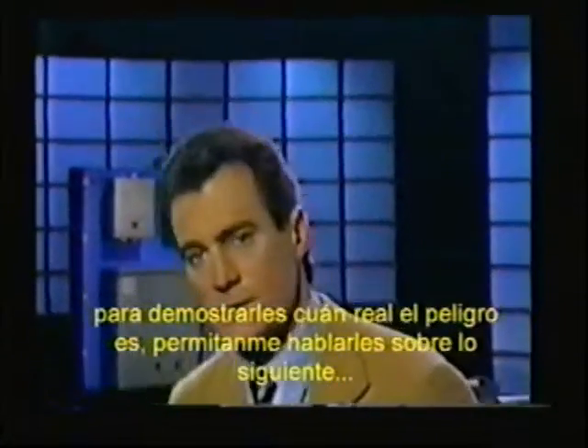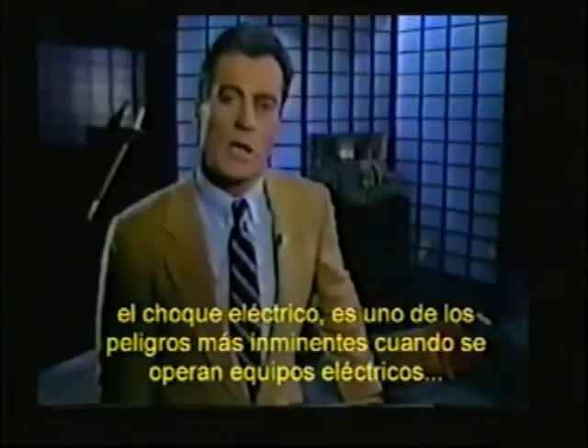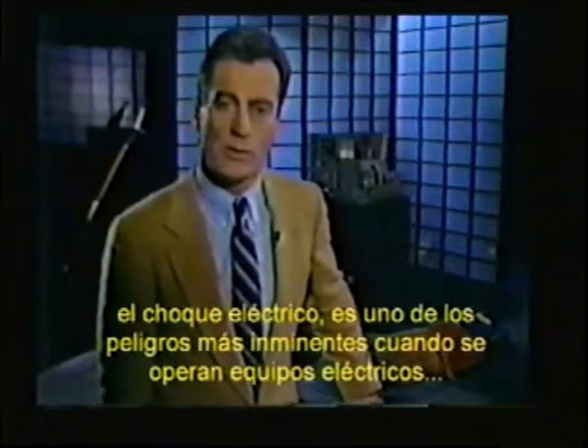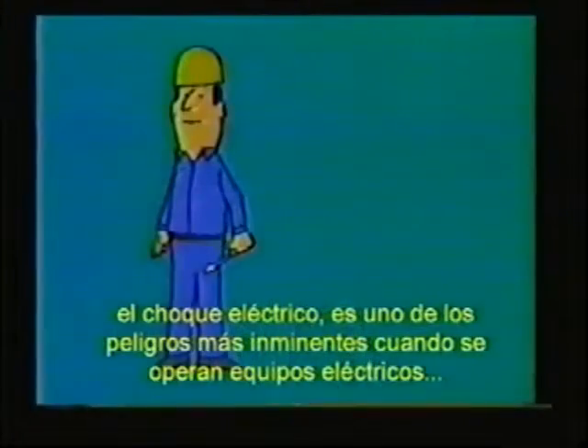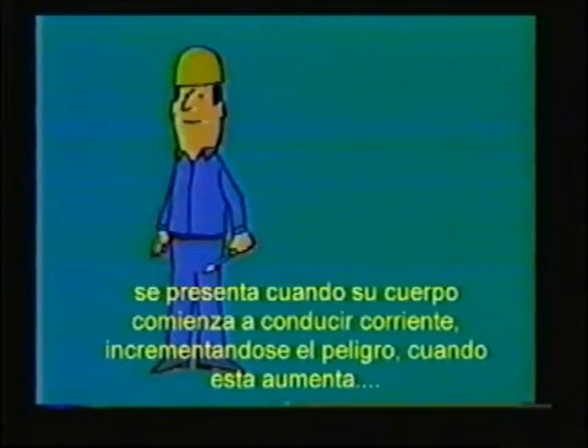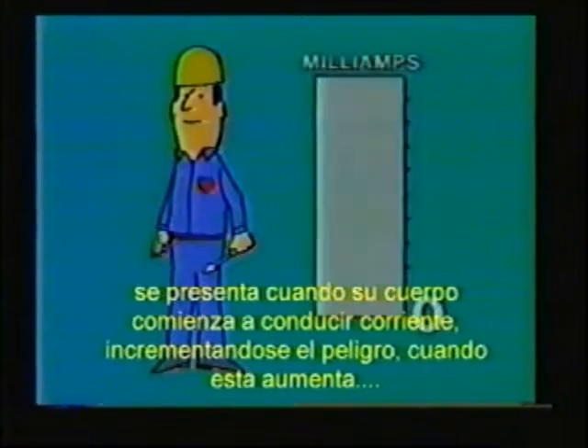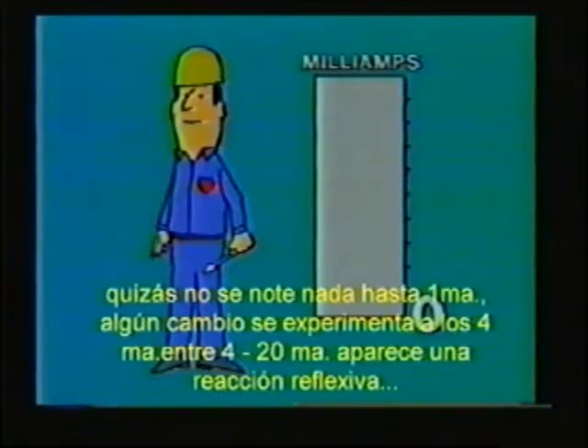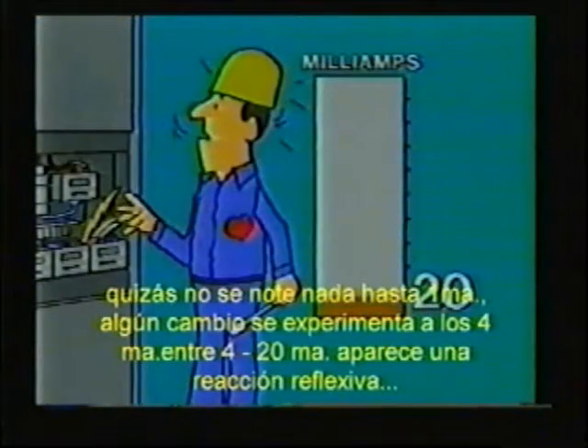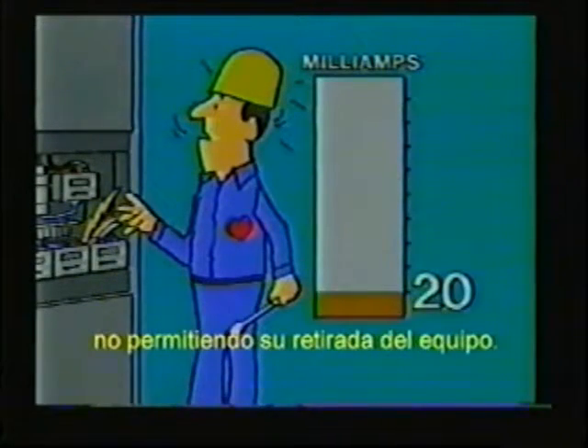Electrical shock is one of the greatest dangers in working with electrical equipment. It occurs when all or part of your body becomes a conductor of electricity, and the danger increases as the current increases. You probably wouldn't notice a current of less than 1 milliamp. However, a surprise effect may be experienced up to approximately 4 milliamps.